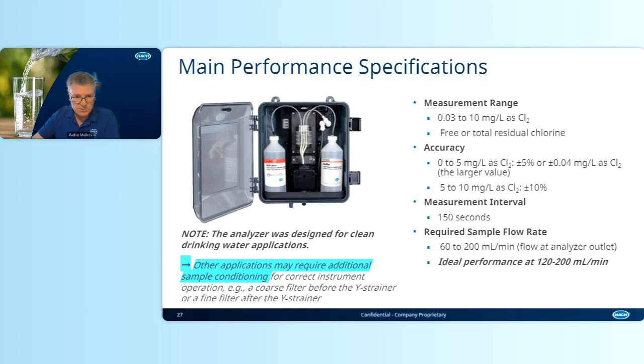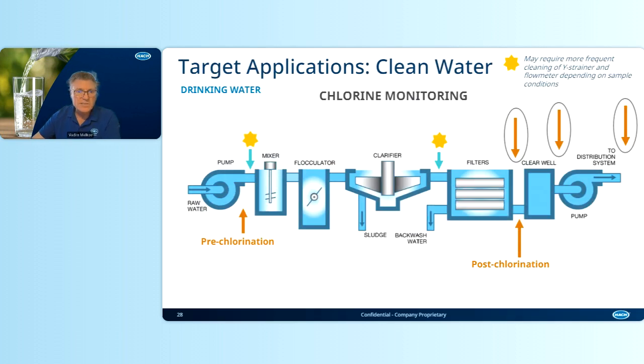Now, back to the applications. As I said, this analyzer was designed for clean drinking water applications, being the major target application pool for this machine. It can absolutely be used in other applications. However, they may require additional sample conditioning for correct operation, maybe additional filtration, and we'll talk about this in the next few slides. But at this point, let's focus on the essential applications for the CL17 SC analyzers. Target applications: clean water, as I mentioned. Those are represented by drinking water post-filter and post-chlorination. You can see here on the right-hand side the measurement points depicted by the encircled arrows.